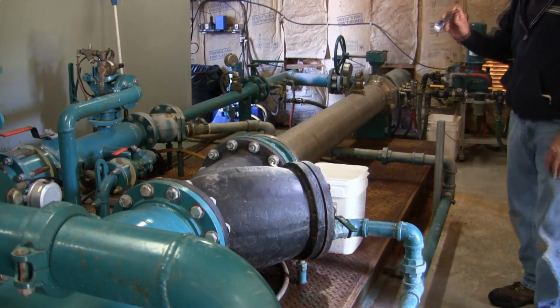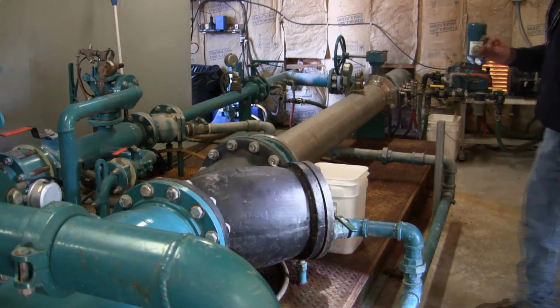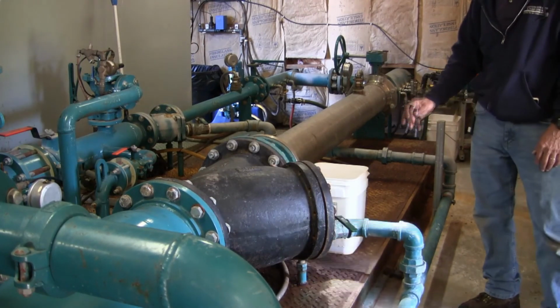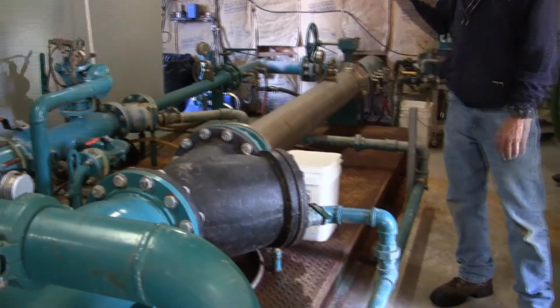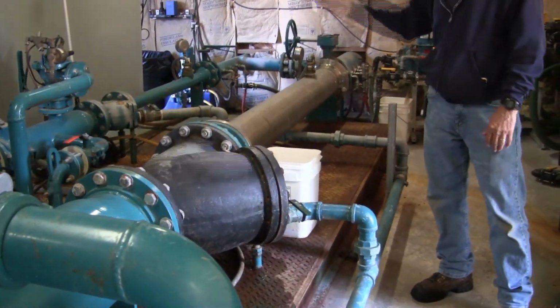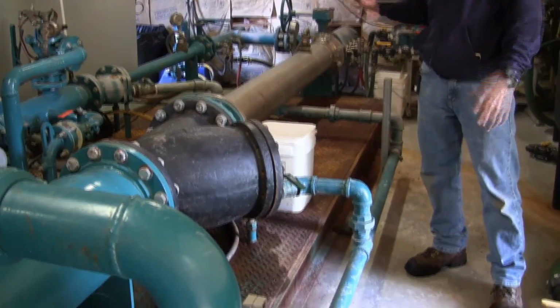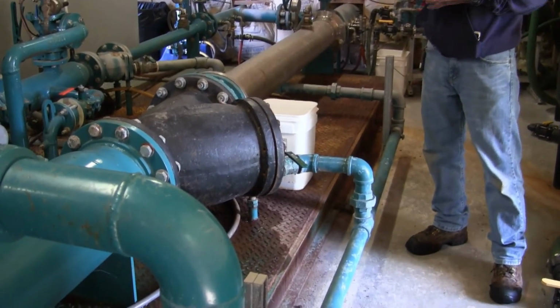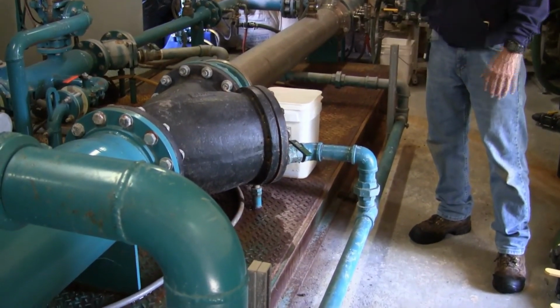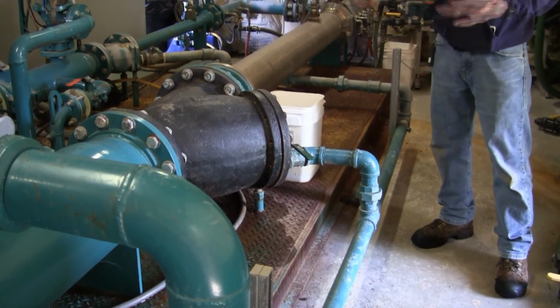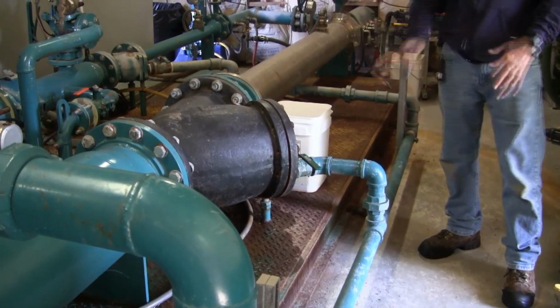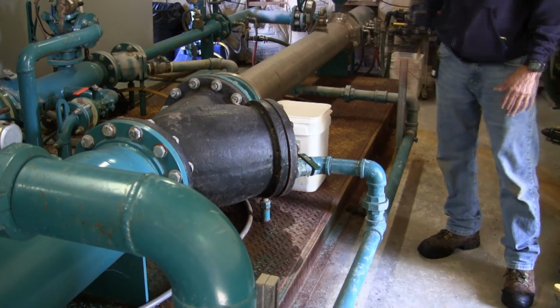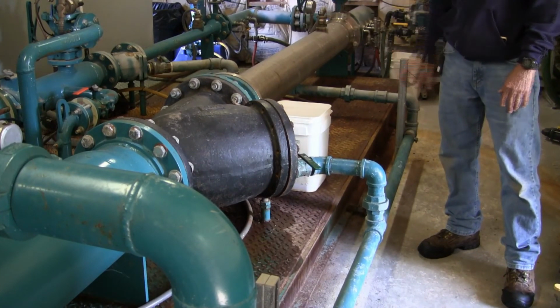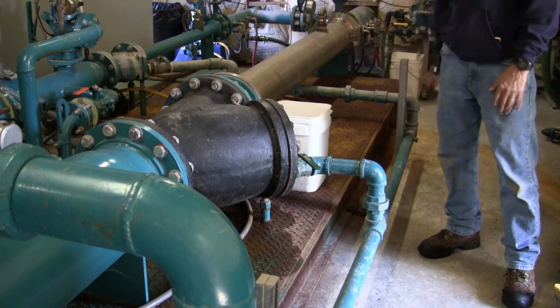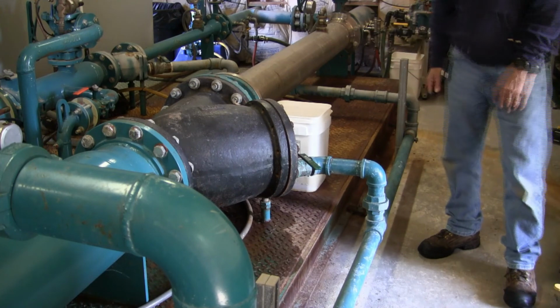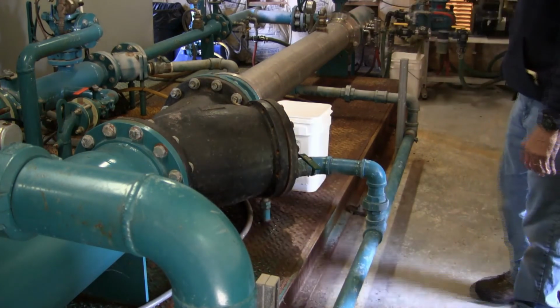This station has a Y strainer. There's a lot of stations that have an electric valve, where after a certain amount of time it can be set up on a timer if you're watering a program. After 30 minutes or 45 minutes or however long, it's programmable, where it will open up and flush the Y strainer. This one, they just open manually whenever they get in there, just to flush out that strainer.